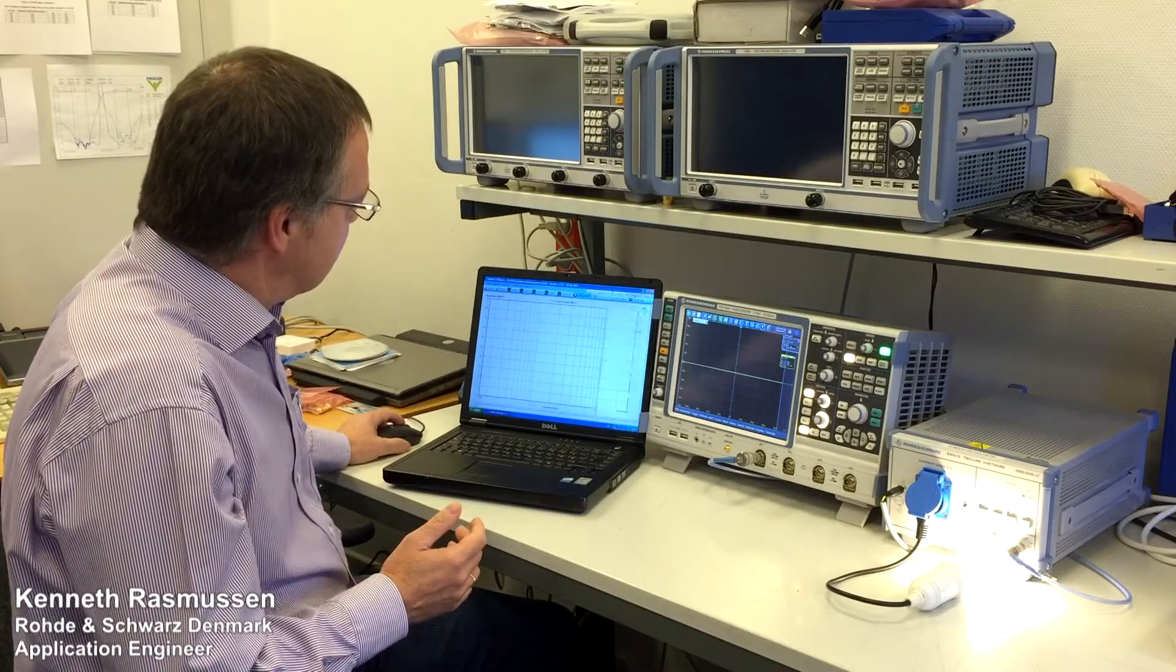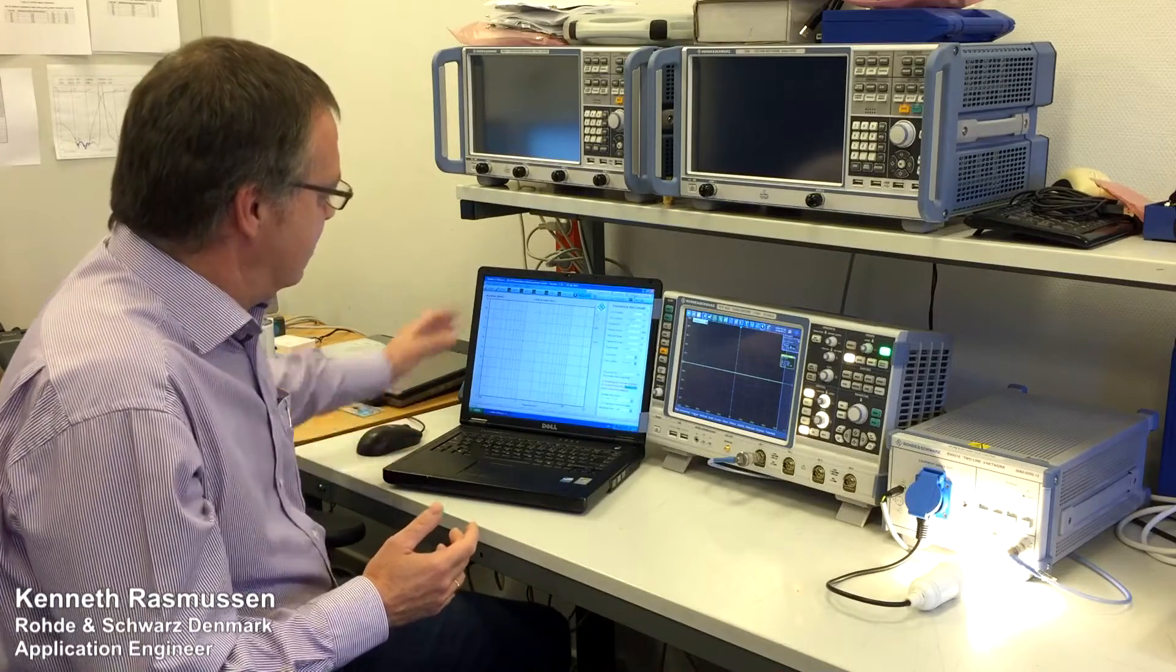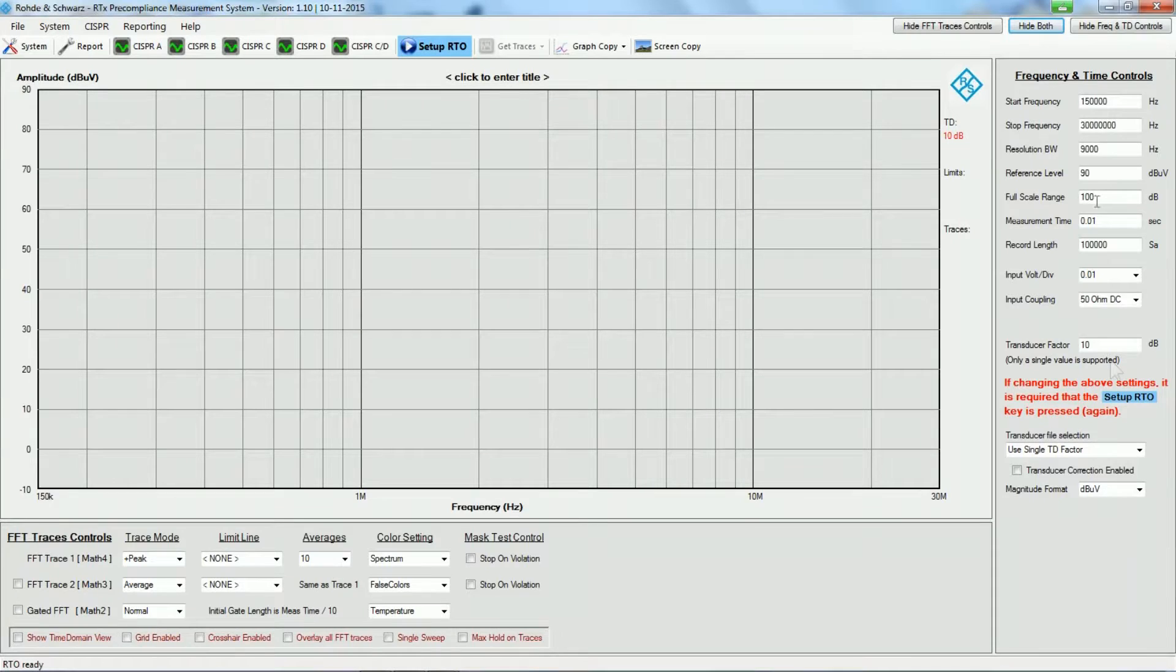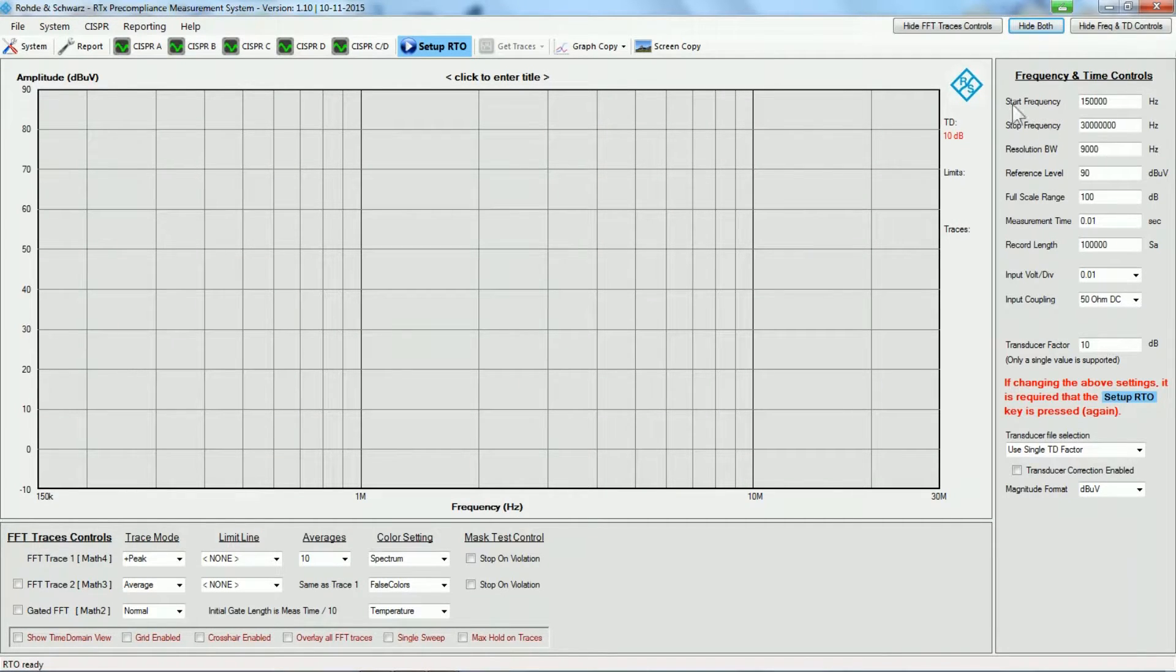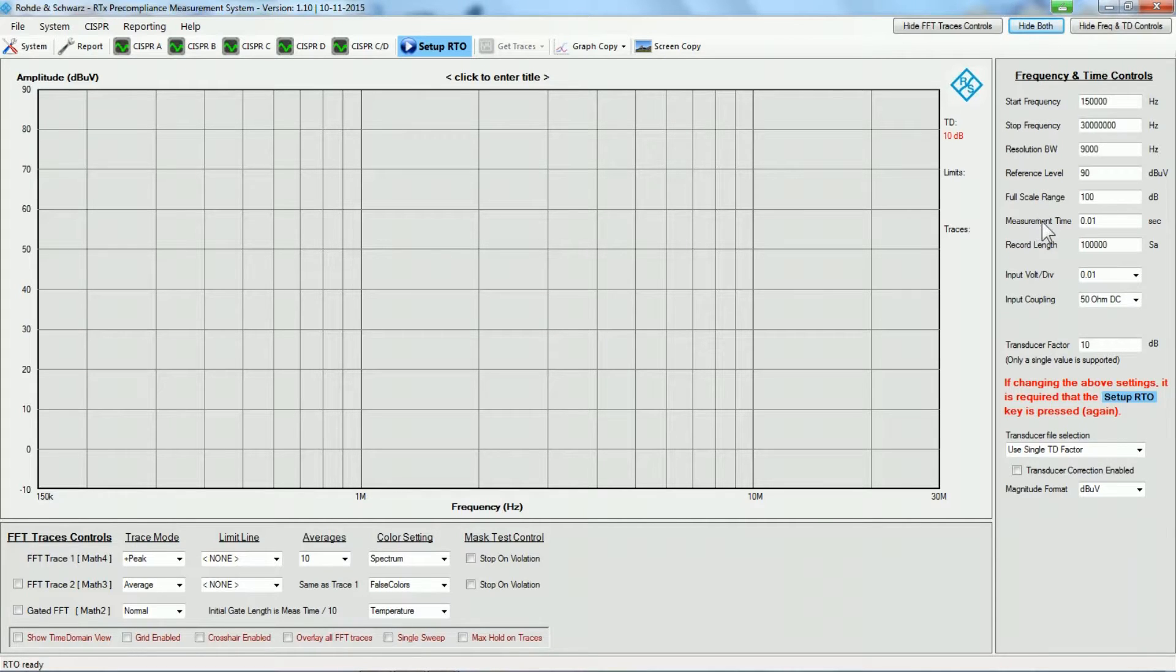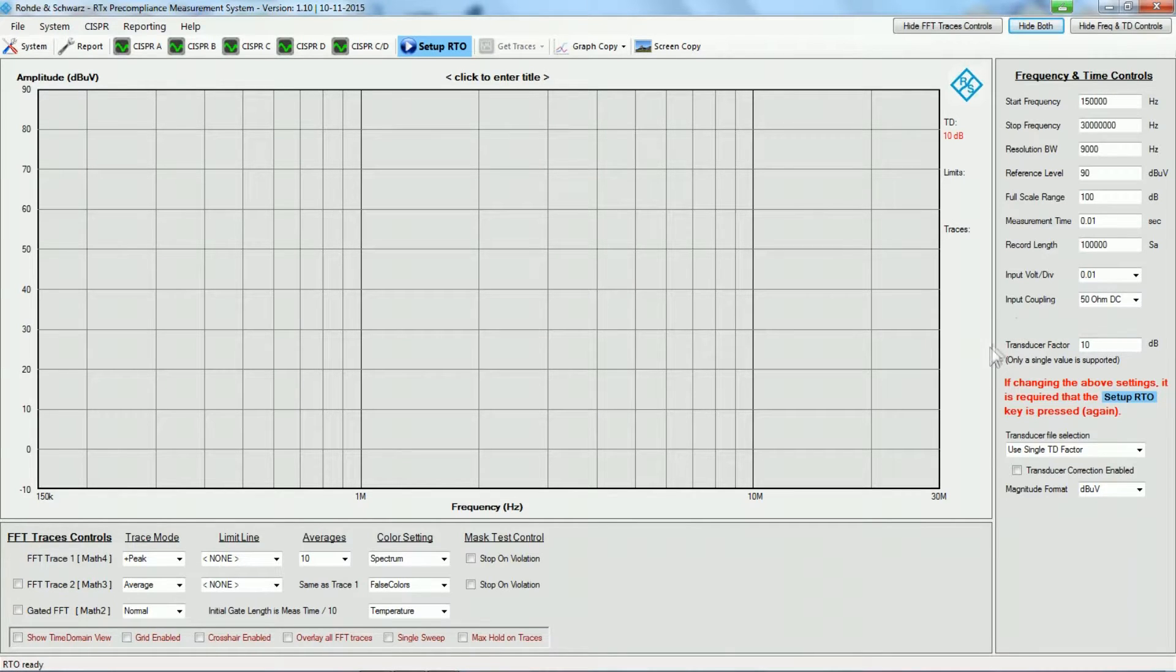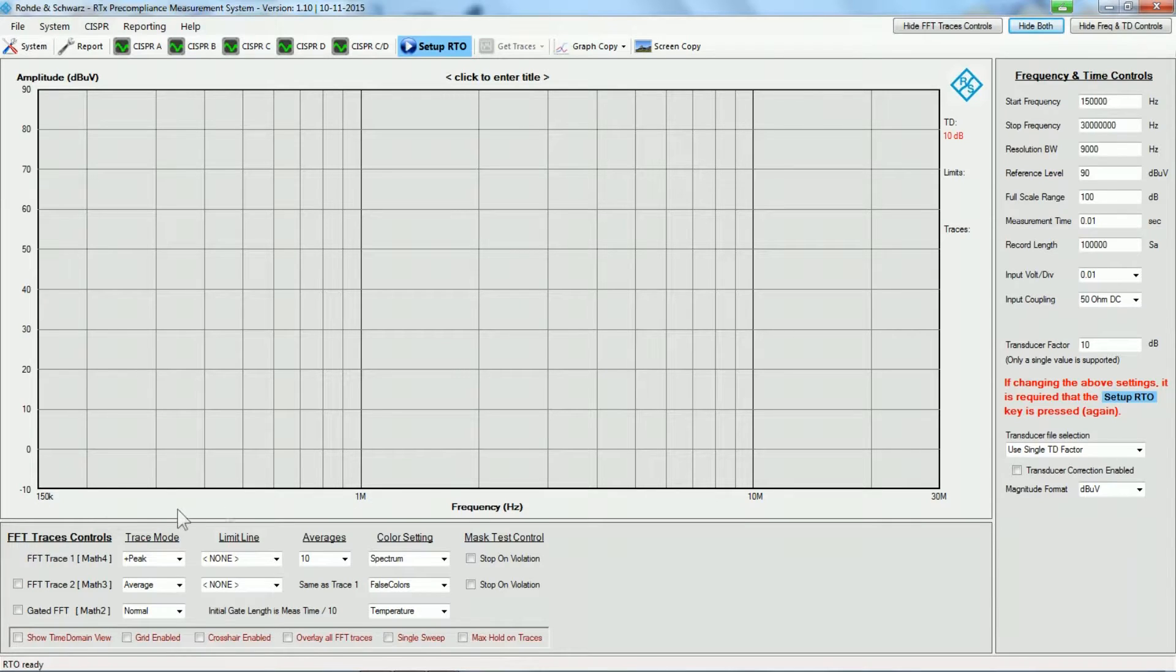This software application has two sets of controls. One set where you can control the frequency ranges, the settings, the time settings, the FFT settings and so on, also setting up the transducer factor for the LISN network. Another set of controls is down here for the different traces.